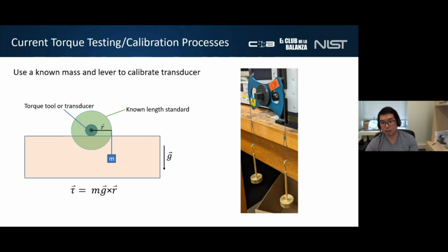And for lower value torques, a torque tool is tested by using known mass and length values and simply hanging the mass off of a known lever arm, then reading the value displayed on the torque tool. So this can be kind of difficult, it's very finicky, time consuming, very inefficient, and still ultimately traceable to old school length and mass standards.